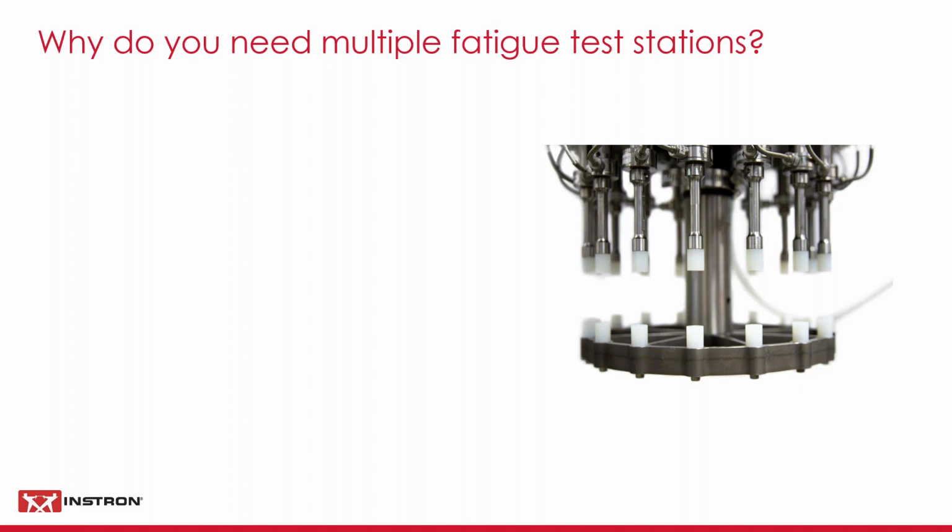Obviously, with that, I don't know about other manufacturers, but we provide live displays so that you can put up the force acting on every one of those individually, and you can be absolutely sure that there's nothing untoward happening, no distortion, so you haven't put one in and knocked the one next to it with your finger or your tweezers.